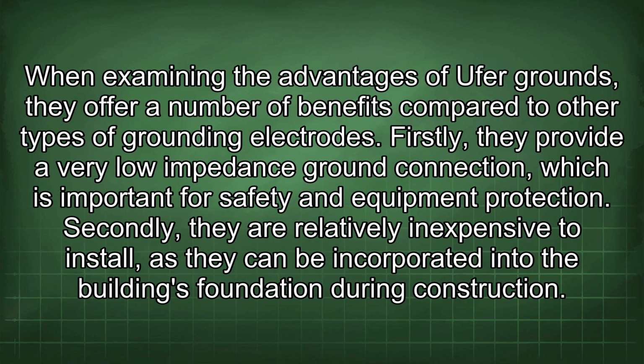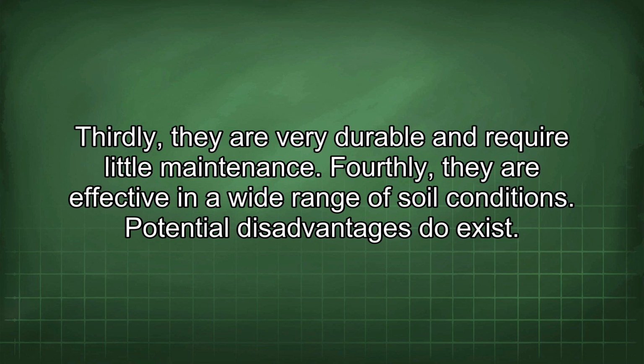When examining the advantages of Ufer grounds, they offer a number of benefits compared to other types of grounding electrodes. Firstly, they provide a very low impedance ground connection, which is important for safety and equipment protection. Secondly, they are relatively inexpensive to install, as they can be incorporated into the building's foundation during construction. Thirdly, they are very durable and require little maintenance. Fourthly, they are effective in a wide range of soil conditions.